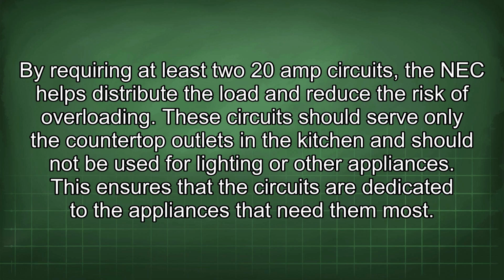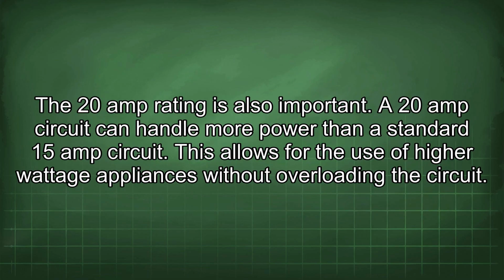These circuits should serve only the countertop outlets in the kitchen and should not be used for lighting or other appliances. This ensures that the circuits are dedicated to the appliances that need them most. A 20 amp rating is also important. A 20 amp circuit can handle more power than a standard 15 amp circuit. This allows for the use of higher wattage appliances without overloading the circuit.